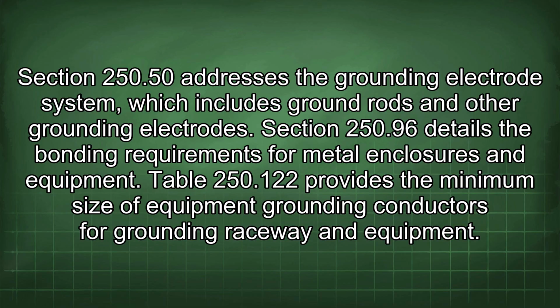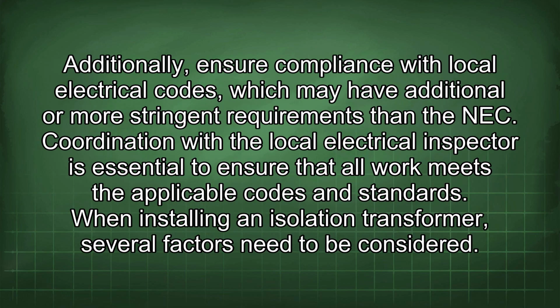Section 250.50 addresses the grounding electrode system, which includes ground rods and other grounding electrodes. Section 250.96 details the bonding requirements for metal enclosures and equipment. Table 250.122 provides the minimum size of equipment grounding conductors for grounding raceway and equipment. Additionally, ensure compliance with local electrical codes, which may have additional or more stringent requirements than the NEC. Coordination with the local electrical inspector is essential to ensure that all work meets the applicable codes and standards.